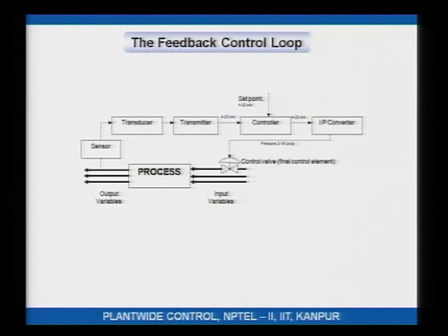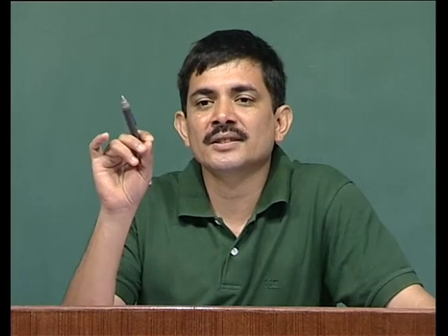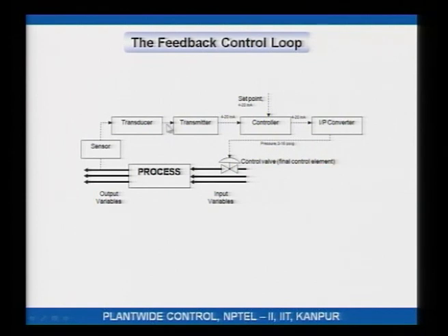Okay. So, the transducer gives a signal which may be in volts, millivolts, etcetera, but this signal needs to be converted into a signal that can be taken by the controller. So, the transducer electrical signal is converted to a 4 to 20 milliamp signal by the transmitter. Okay. The controller does its calculations and then it outputs a 4 to 20 milliamp output signal. Okay.